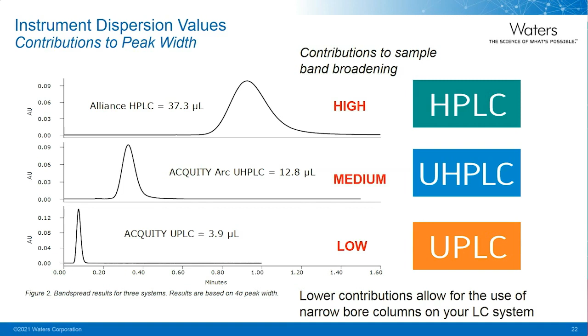Here we have 3 columns with different internal diameters packed with 2.7 micron particles. We've run the sample separation on each column using an Alliance HPLC, which has a high dispersion value. As you can see from the chromatography, as the column ID is reduced, the peak shape and resolution get worse. Some may think it's the column, but it's not. The band spreading from the system is swamping out the efficiency.